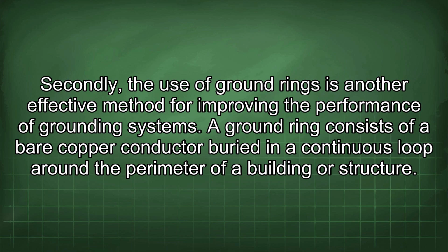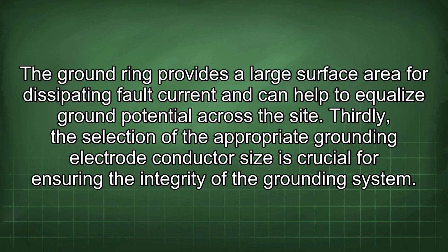Secondly, the use of ground rings is another effective method for improving the performance of grounding systems. A ground ring consists of a bare copper conductor buried in a continuous loop around the perimeter of a building or structure. The ground ring provides a large surface area for dissipating fault current and can help to equalize ground potential across the site.